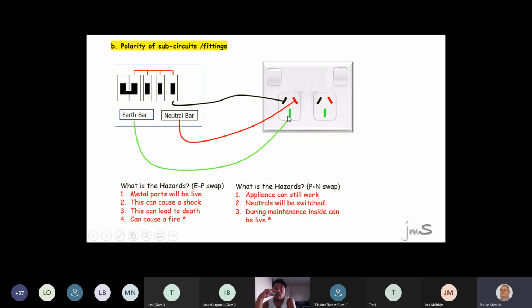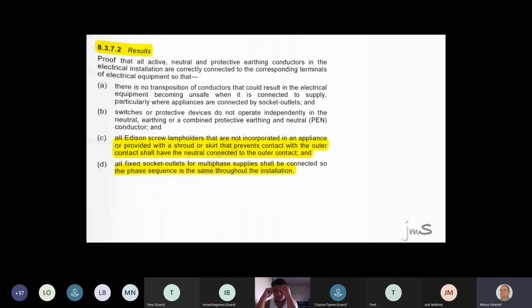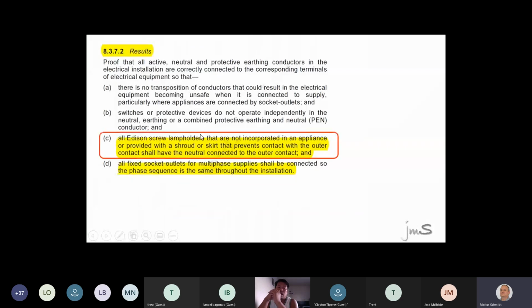But my question to you guys is, if phase and neutral are swapped, it's very important to ensure that if polarity is swapped, you're not going to scratch inside any appliances or fittings. Now, before you do that, as a Sparky, do you check that phase is phase, neutral is neutral, and earth is earth? What do we call that test? Insulation resistance test or a polarity test? Well done.